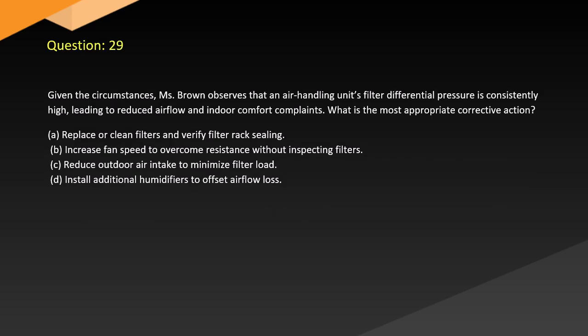Question 29. Given the circumstances, Brown observes that an air handling unit's filter differential pressure is consistently high, leading to reduced airflow and indoor comfort complaints. What is the most appropriate corrective action? A. Replace or clean filters and verify filter rack sealing. B. Increase fan speed to overcome resistance without inspecting filters. C. Reduce outdoor air intake to minimize filter load. D. Install additional humidifiers to offset airflow loss.